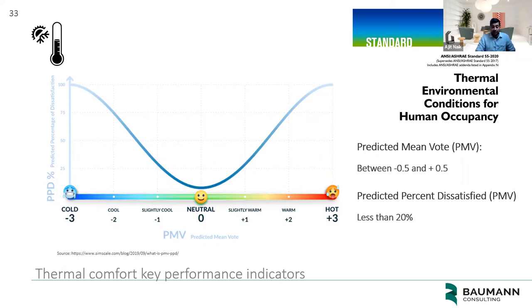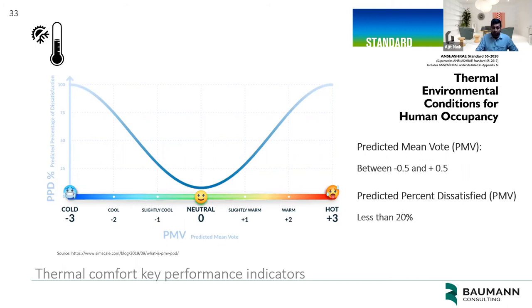Modern standards say that a predicted mean vote of negative 0.5 to positive 0.5 is generally considered comfortable, and as long as less than 20% of people are predicted to be dissatisfied, that's also considered comfortable. There are criticisms of the study — it's not really applicable for very high activity levels over about 1.5 met, it's only applicable for healthy adults and doesn't apply to older people or babies — but there are also studies that validate its applicability for the range where it applies. Even today, ASHRAE Standard 55 still uses this granddaddy of comfort metrics. It's the most common thing you'll run into.